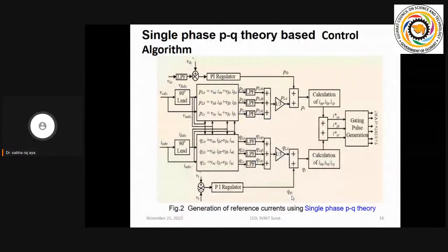This is the one simple control. In this case, what we have done, we have sensed the voltage. Also, we have sensed the DC link, and we have regulated the error between the sensed value and the actual required value. For that, we need to tune the values of K_P and K_I. Then the output of that one you can consider as a signal. If the other components are in terms of power, you can consider that one in power. If the other components are in terms of current, you can consider it as current. Finally, we can say that it is a signal only.